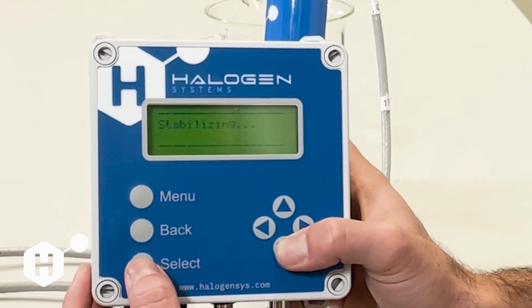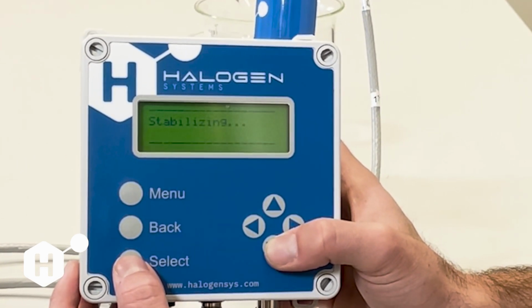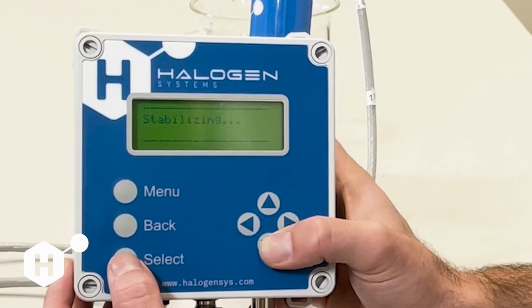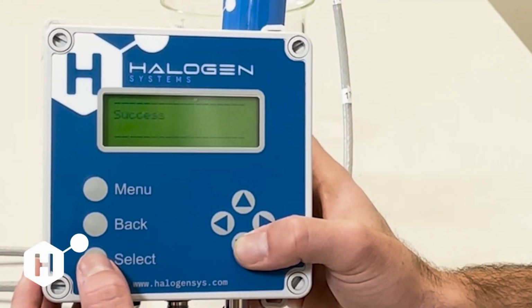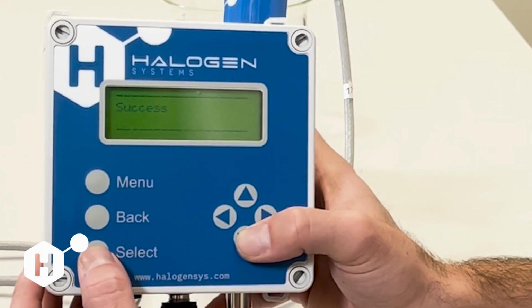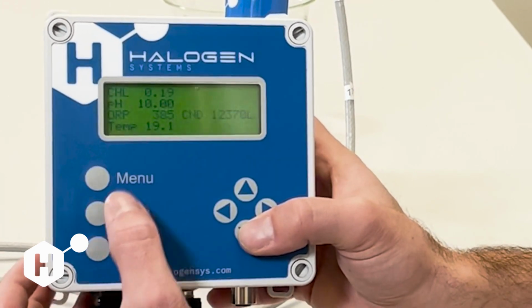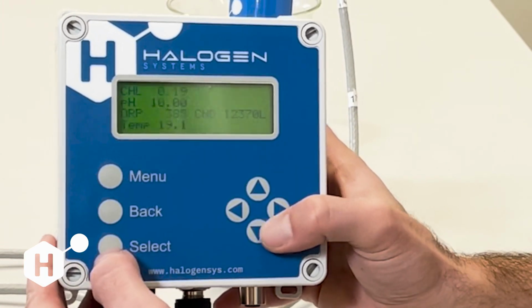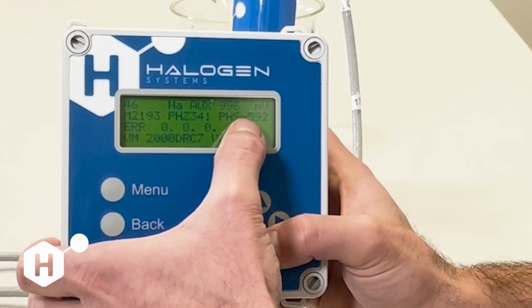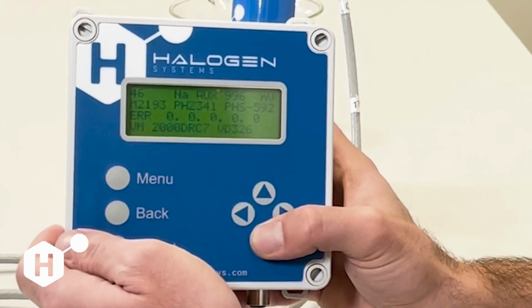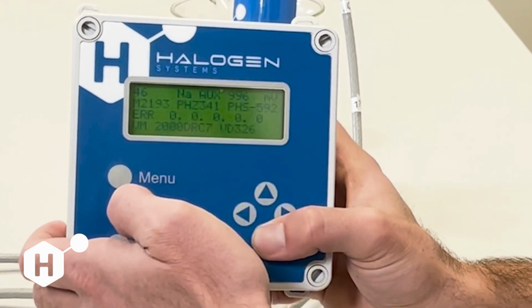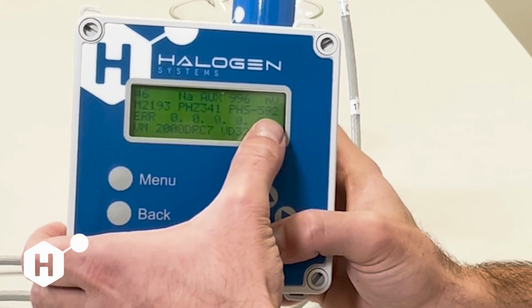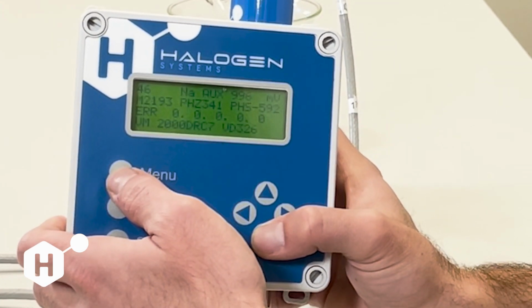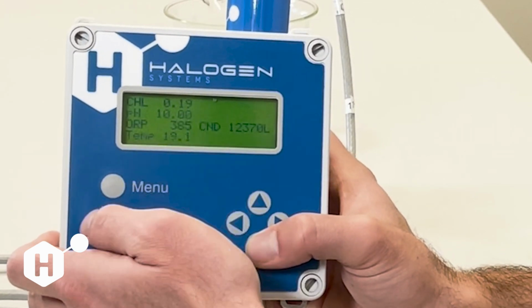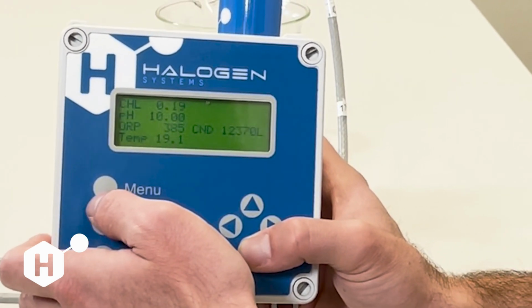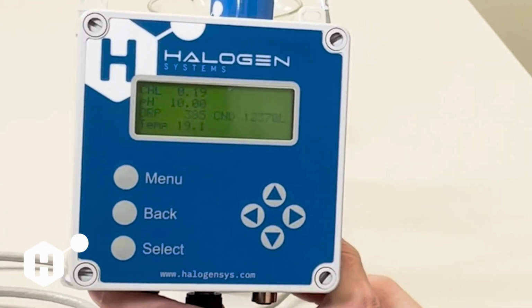You're going to see stabilizing. This could happen for up to a minute before you get a confirmation of calibration. And success. So to confirm that our pH calibration was successful, we're looking for pH to be 10. The next thing we're also going to look at is our pH slope, to see if it has changed from negative 59.2. It might take up to 1 cycle for this slope to update. I'm confident that this 10 buffer calibration was successful because there we are already measuring 10 pH. However, I will give it one more cycle to confirm that that measurement is stable.